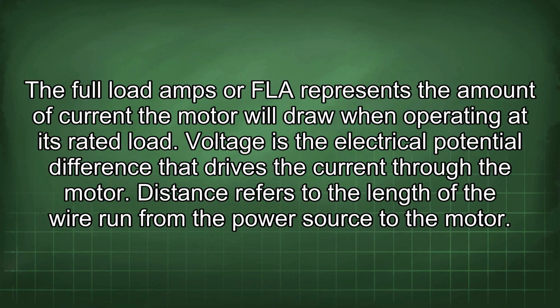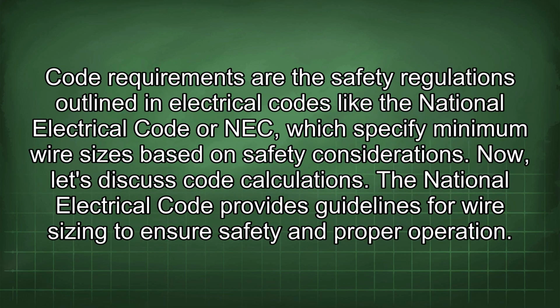The full load amps, or FLA, represents the amount of current the motor will draw when operating at its rated load. Voltage is the electrical potential difference that drives the current through the motor. Distance refers to the length of the wire run from the power source to the motor. Code requirements are the safety regulations outlined in electrical codes like the National Electrical Code, or NEC, which specify minimum wire sizes based on safety considerations.